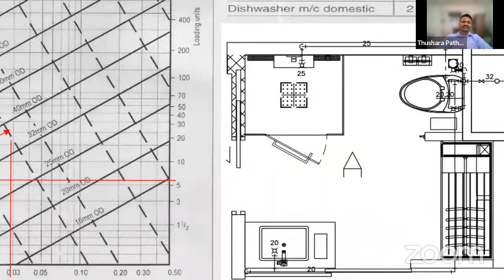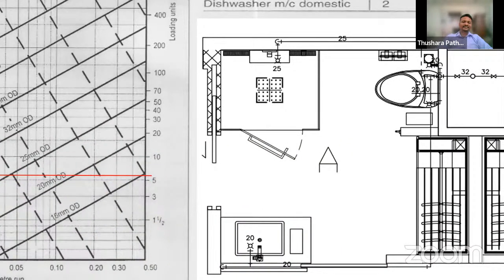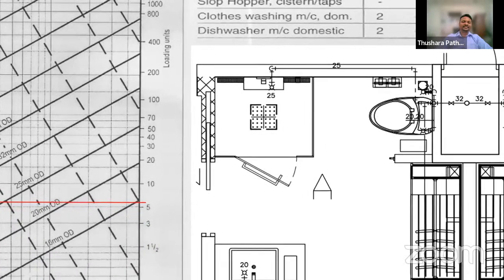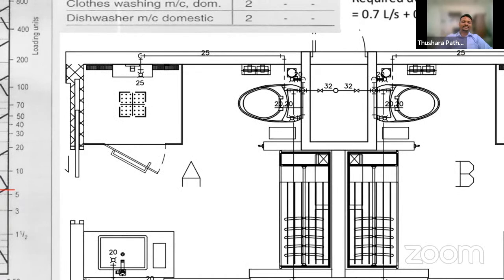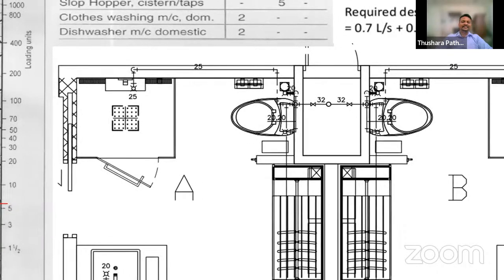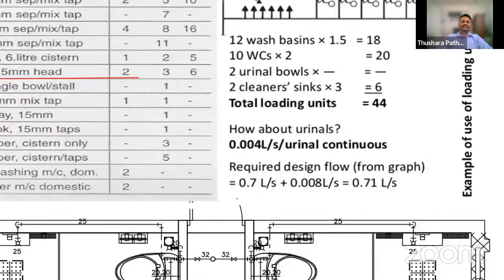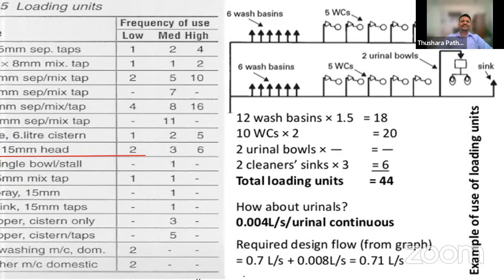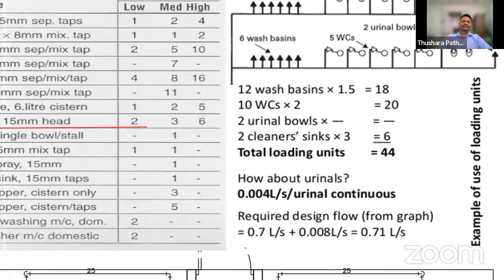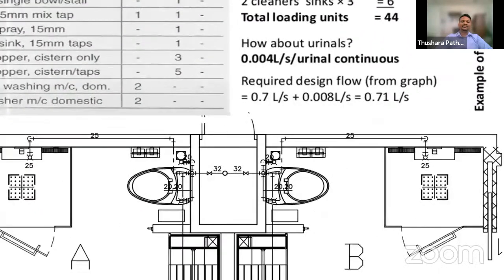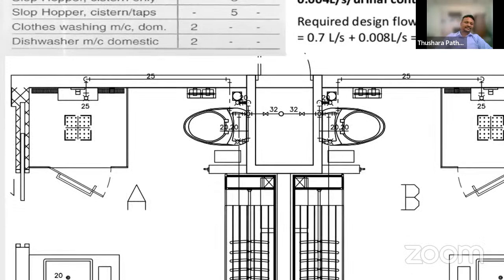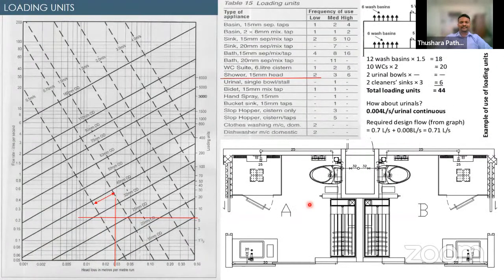For a guest bathroom, a 25mm pipe size is sufficient for a shower. Once all branch pipes are sized in this manner, we can size the distribution pipe by adding all the loading units of appliances connected to a particular branch, reading the flow rate from the graph, and calculating the pipe size. Similarly, for transfer or booster pump head estimation, we sum the elevation difference and the pump constant multiplied by Q², plot the system curve, then overlay manufacturer pump curves to find the pump operating point where the two curves intersect, selecting the best pump based on efficiency and power consumption.